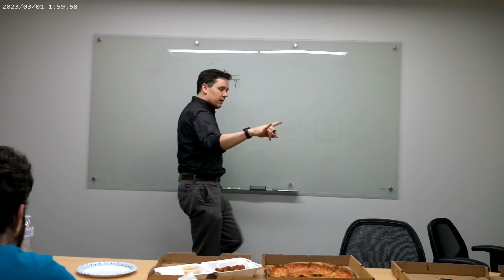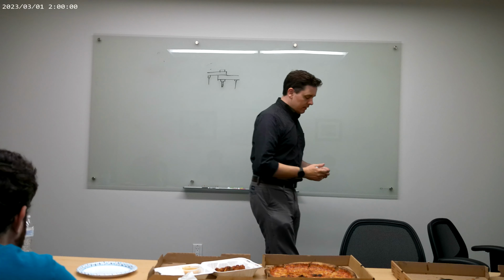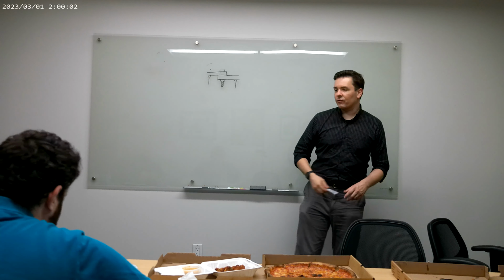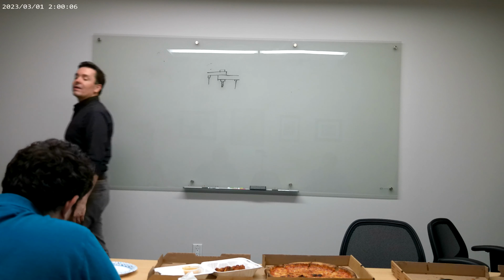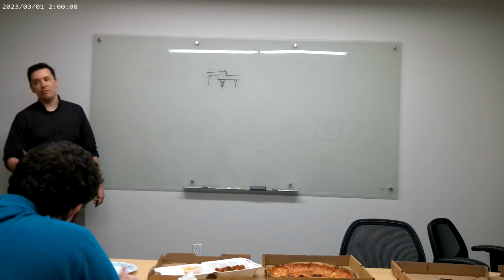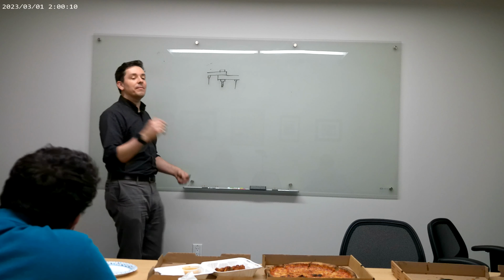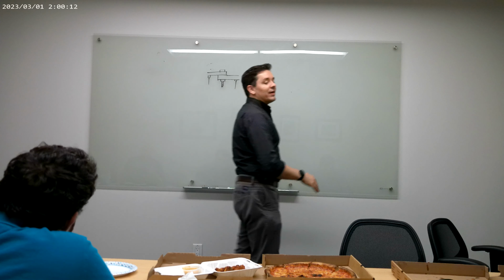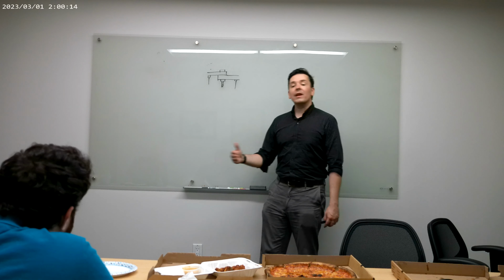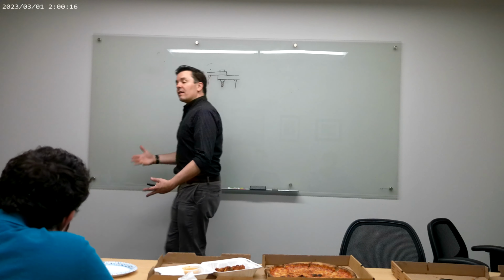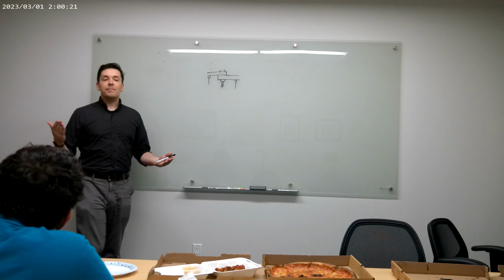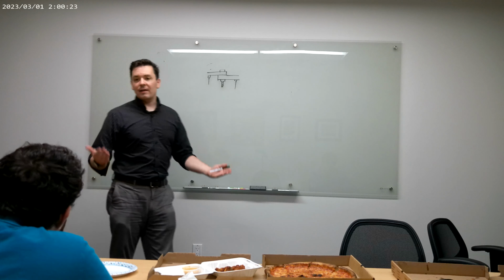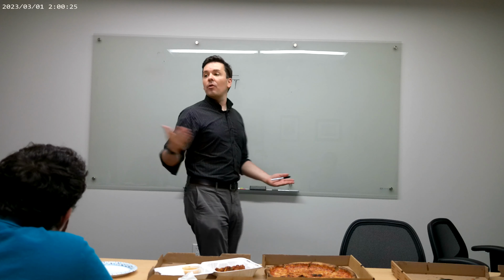Now, does the NETA guide tell you what are good and bad values for a Ductor? I'll give you a spoiler because we're running low on time. No, it does not. It does not give you absolute values because the range of acceptable resistances varies pretty wildly. What it does say is that for things like multi-pole mechanisms, such as a circuit breaker, you should vary by no more than 50% high to low, pole to pole.